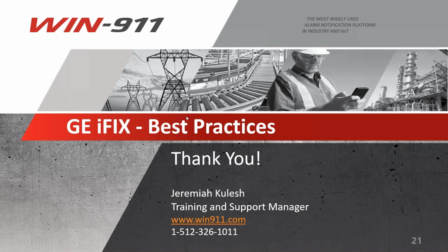So Rosa, yeah, that's a difficult situation created by what you guys need, right? From the WIN-911 call out standpoint, your two options are going to be stop the strategy, which is stop the call out list when it's acknowledged, or stop it when it's terminal, which is acknowledged and inactive.